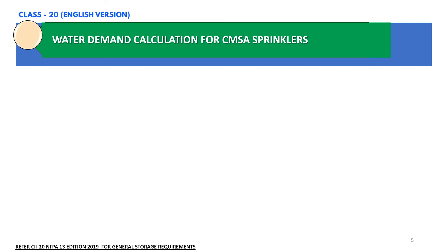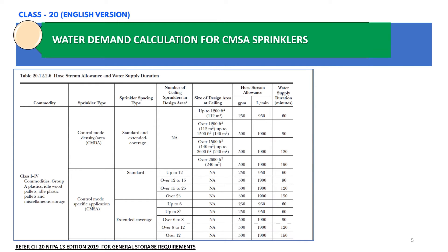Now we are going to calculate the hose stream allowance and also the water supply duration. I have extracted a table from NFPA 13 which shows the hose stream allowance and water supply duration based on the commodity classification. In our scenario, we have class 4 commodity and we are considering CMSA sprinklers. The design area uses 15 sprinklers, which falls in the row for over 12 to 15 sprinklers. Based on this row, the hose stream allowance is 500 GPM and the water supply duration is 90 minutes.